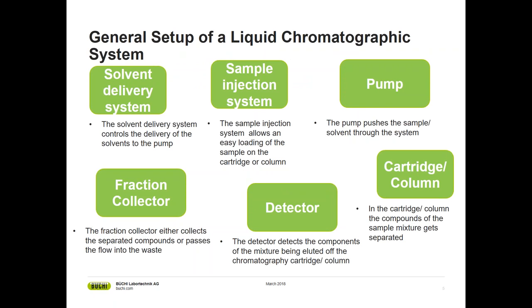What is the general setup of a liquid chromatographic system? First, there is a solvent delivery system, which controls the delivery of solvents to the pump. There is a sample injection system, which allows loading of the sample onto the cartridge or column. Then there is a pump, which pushes the solvents and sample through the whole system including the cartridge — and this is where the separation happens. The next step is detection of the components coming from the cartridge, and finally, in the fraction collector, the compounds are either collected into glass tubes or passed into the waste.